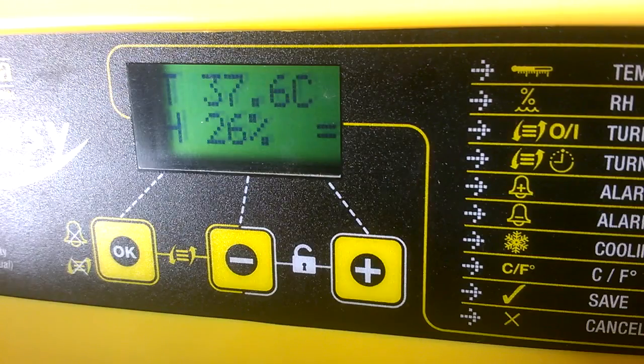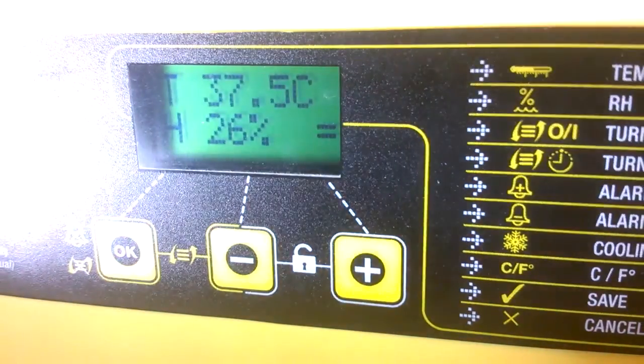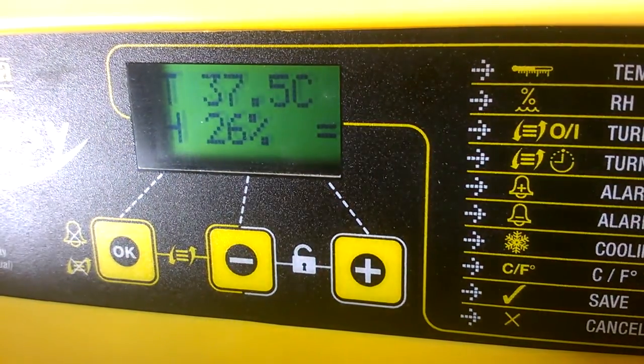You've now taken a reading on your thermometer 30 minutes later after the temperature is stabilized, and you are comparing it to the reading on your digital menu, and you have decided that there is more than a 0.2 degree difference. Therefore, what you now want to do is to bring the reading that you have here on your digital menu in line with the reading that you have on your thermometer. So you need to go into the calibration menu.